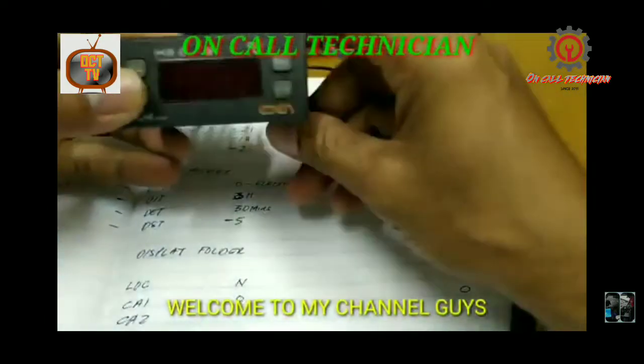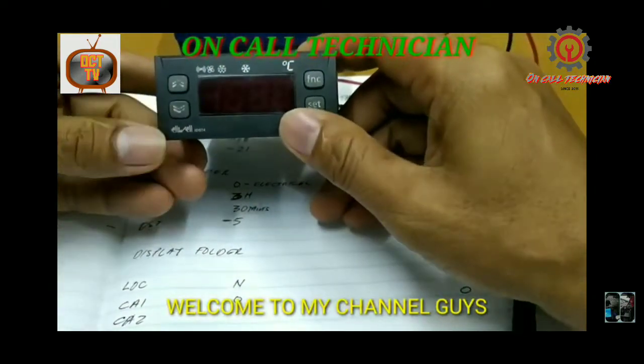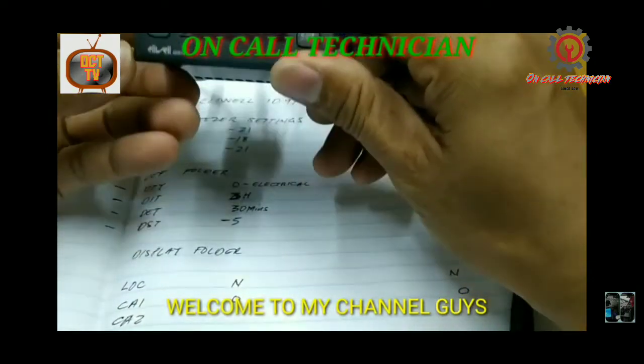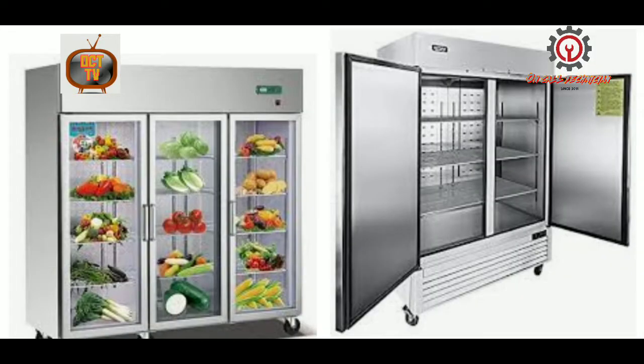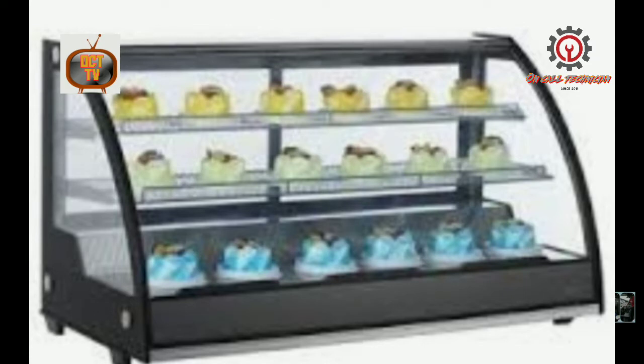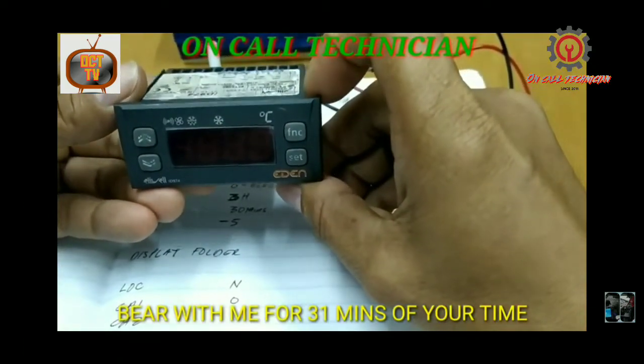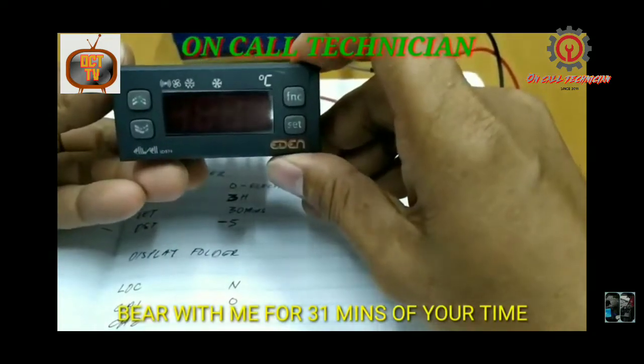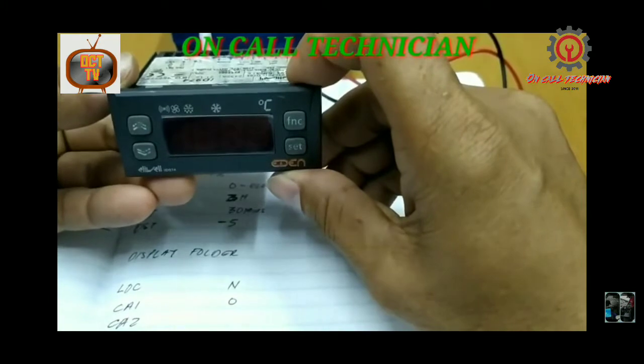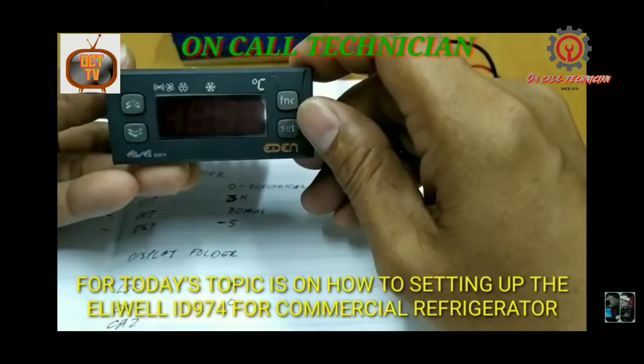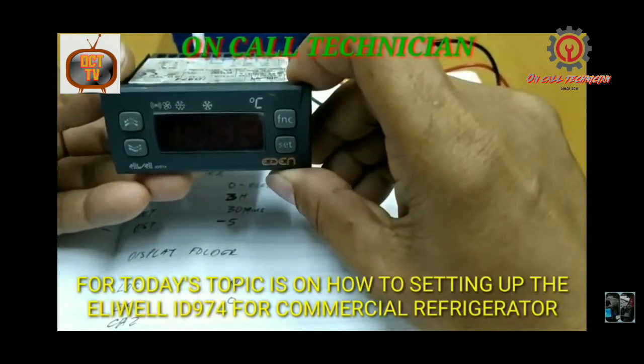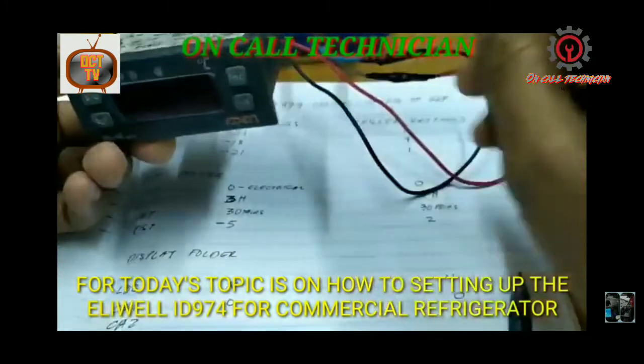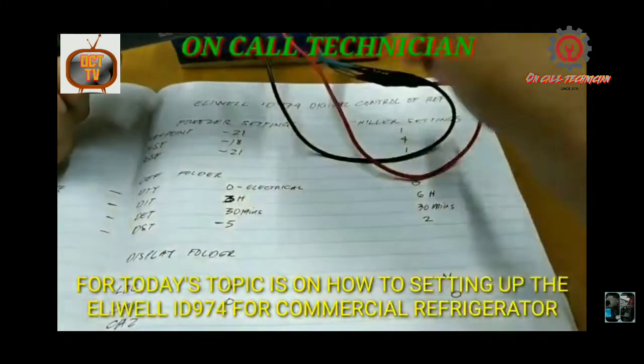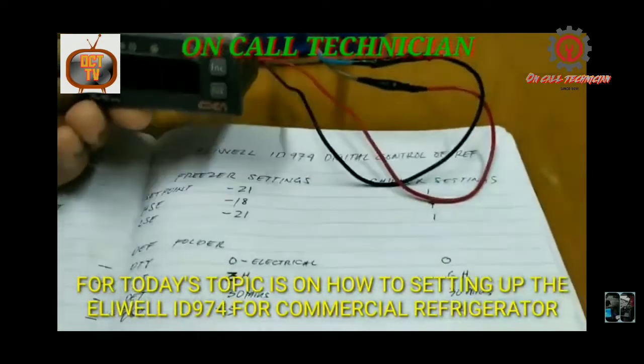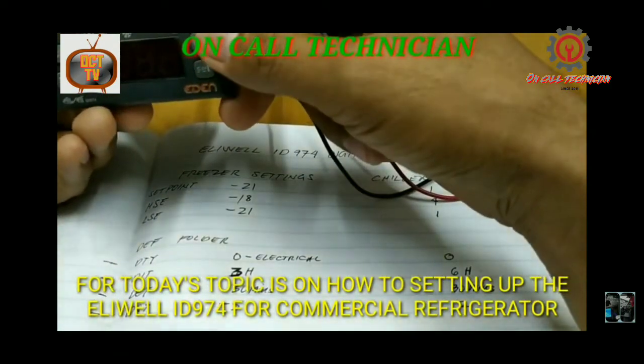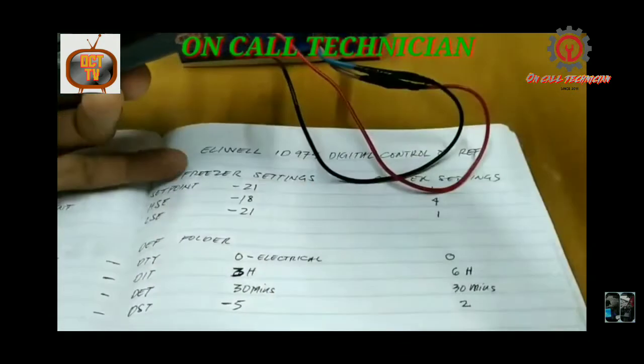Today we're going to discuss setting up the Eliwell ID974. Most of our commercial refrigerators are using digital control, and one of them is this Eliwell, a product of Italy. There is a big advantage in using it because aside from the display temperature, you can set the defrost time as well as the on and off of the compressor and the fan motor. For example, in defrost mode, if you want to turn off the fan motor, you can do it.